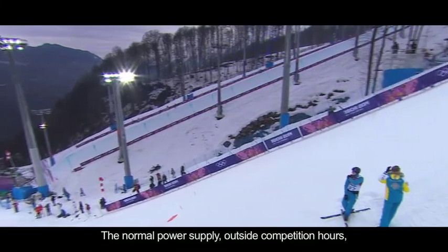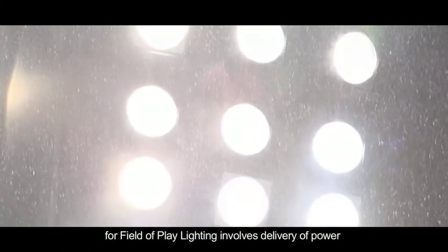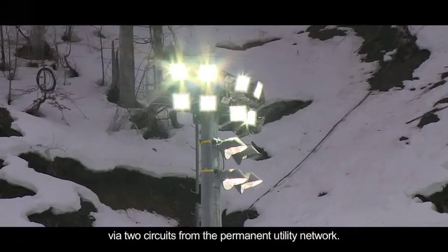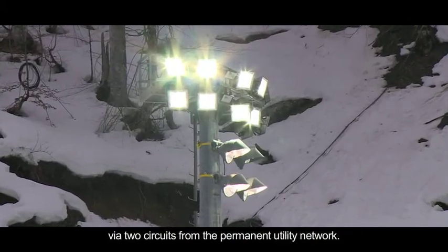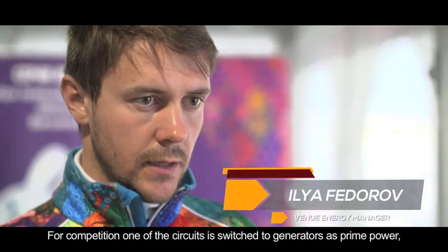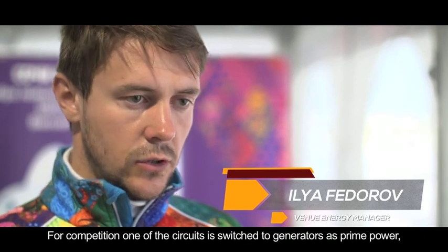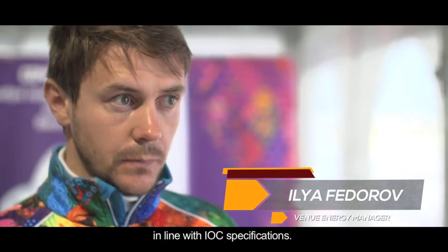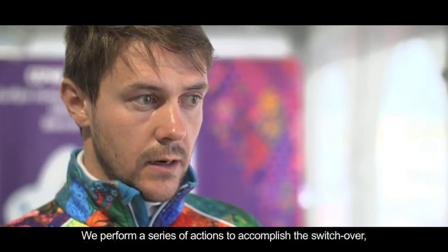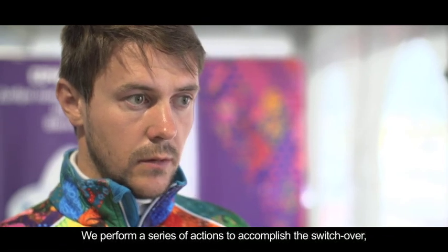The normal power supply, outside competition hours, for field of play lighting, involves delivery of power via two circuits from the permanent utility network. For competition, one of the circuits is switched to generators as prime power, in line with IOC specifications. We perform a series of actions to accomplish the switchover.